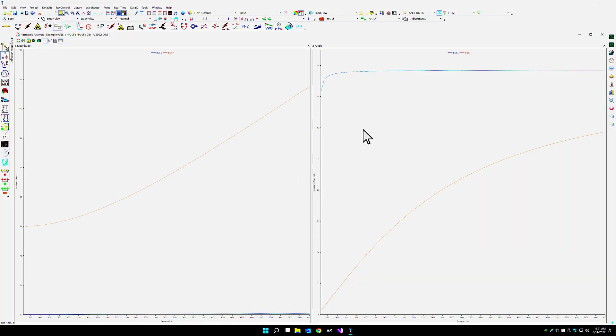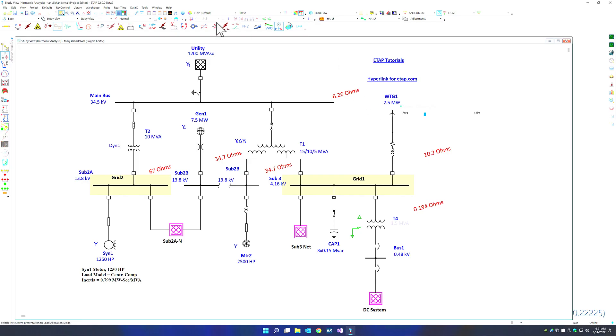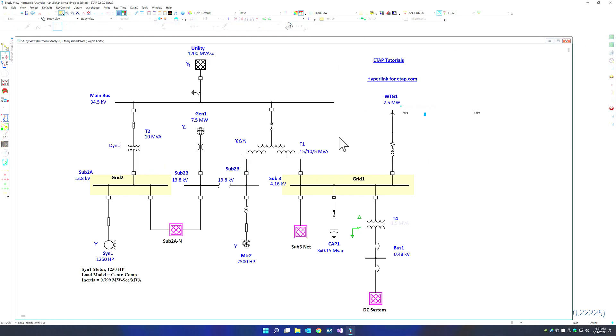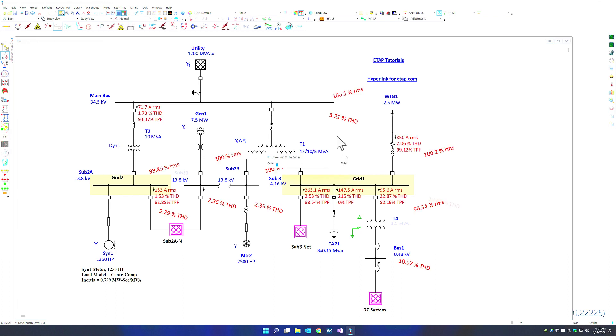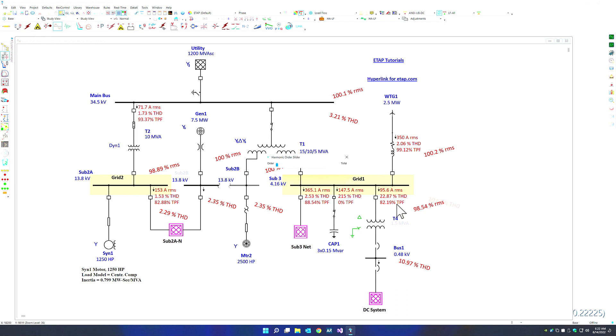Including the positive and zero sequence frequency scan, you can also run the harmonic load flow within ETAP. The program now gives you the current total harmonic distortion as well as the total power factor. The study report gives you the displacement power factor, which is the power factor in the system without harmonics, and the total power factor based on harmonic content. This is the true power factor that we will be observing at the point of interconnection.